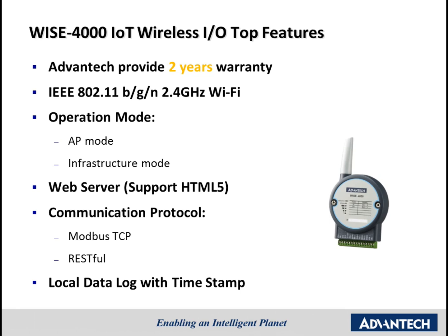Moreover, WISE can be a web server which lets you use a web browser to monitor, control, and configure data. It supports HTML5, which lets the web configuration page fit any size of device. For communication protocols, WISE supports traditional industrial protocols such as Modbus TCP and Modbus RTU, and the web-based protocol RESTful API, which is widely used in IoT environments.